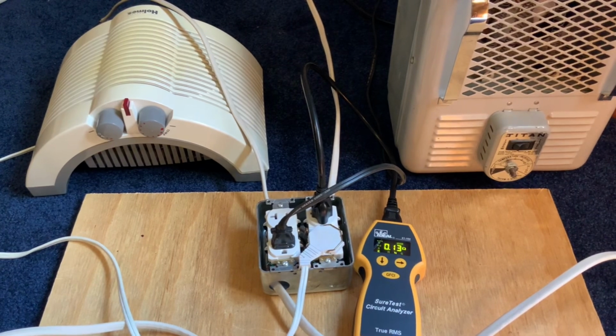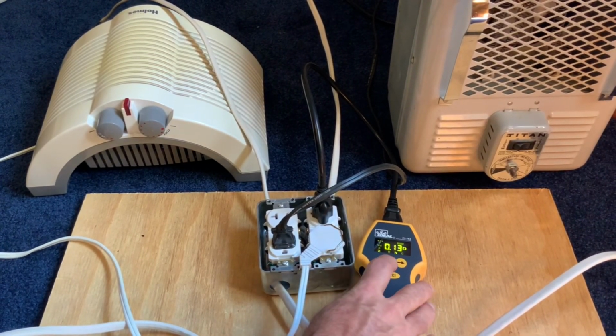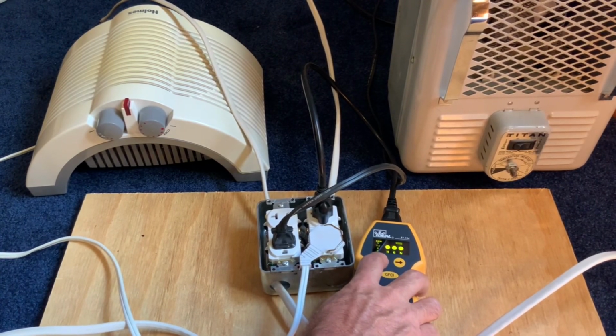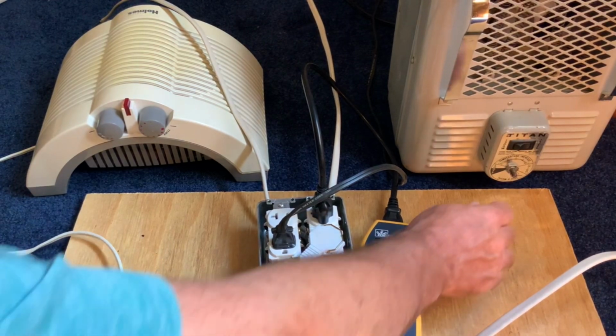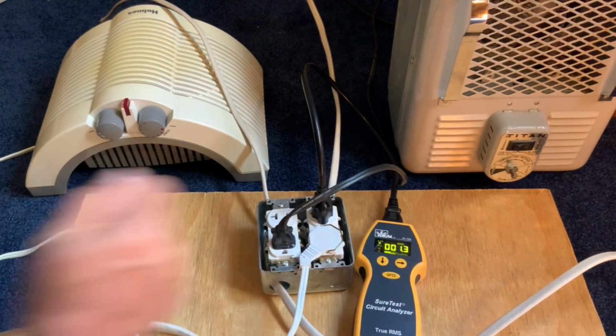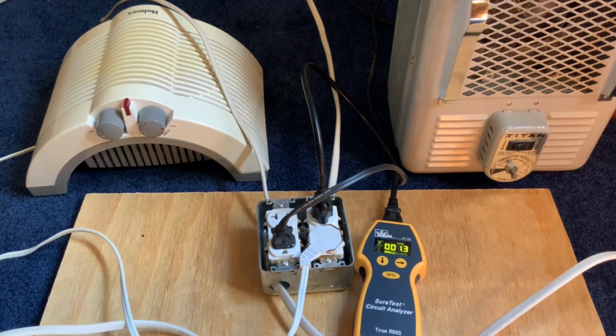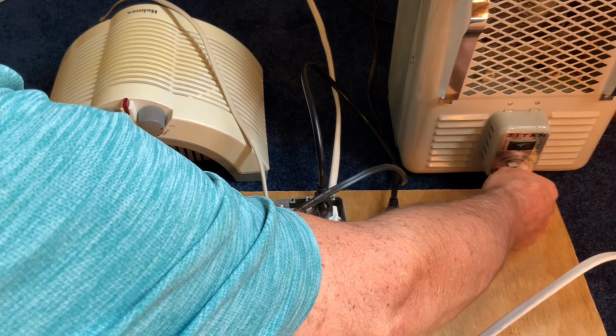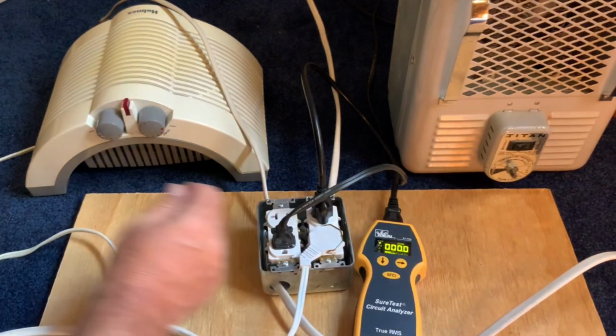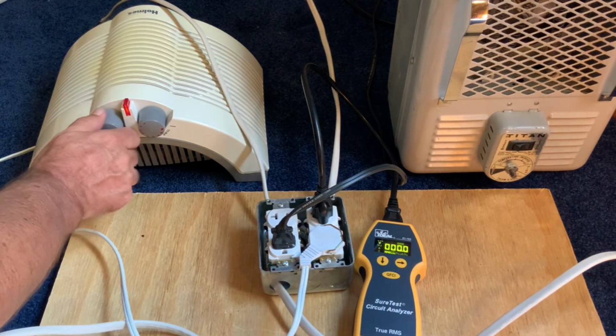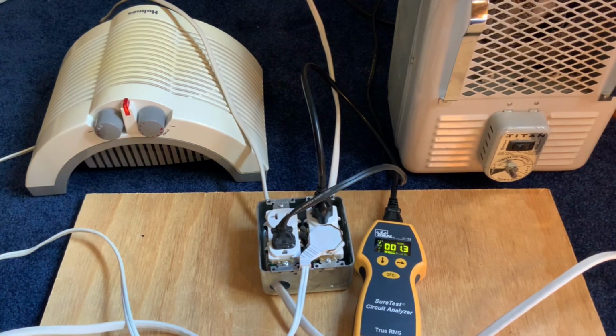I'm only going through about 50 feet of wire, so that gives me 0.13 ohms of resistance in my neutral wire. Each of these heaters draws 10 to 11 amps, so if I put 10 amps through 0.13 ohms, I'm going to see 1.3 volts drop between my ground and my neutral wire because I'm dropping 1.3 volts on that neutral wire. Now, if I turn this heater off and turn the next heater on that's on the other phase, I'll see the same 1.3 volt drop on that neutral wire because they're sharing that neutral wire.